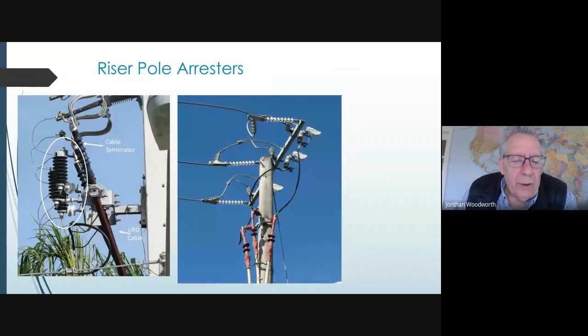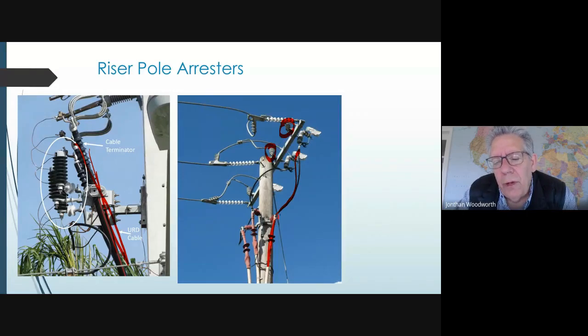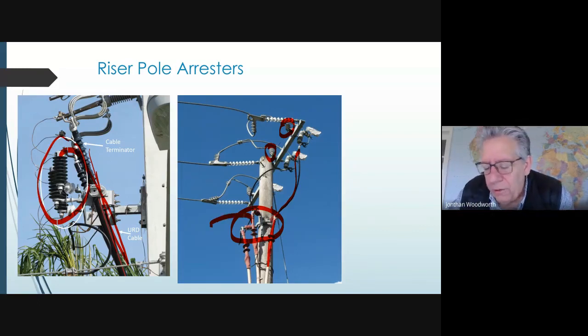This is what it looks like. This is a riser pole arrestor protecting underground cable. This is an example where the underground cable isn't protected quite so well because the arrestor is way up here. Usually when we're trying to protect cable, we try to keep the arrestor as close as possible to the top of the cable. In general, that's a rule of thumb when you're doing surge protection. Always try to keep the arrestors as close as possible to the power system or the piece of equipment you're protecting.